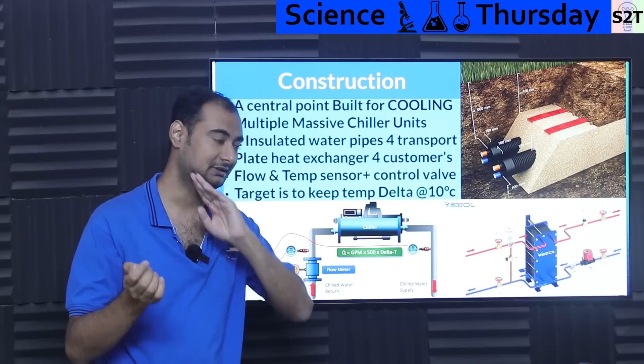So the computer will detect it. The computer is like, okay, let's choke the flow. It will start to slow down the flow, and until it reaches 10 degrees Celsius, it will try to keep it as stable as possible. Now, let's say it opened the max flow, and then you are dumping so much heat into it that the return water, instead of being 15 degrees Celsius, is at 18 degrees or 20 degrees Celsius. They're gonna call you up. It's like, bro, something is wrong. Either your heat exchanger is not up to the scale, or you're overloading it too much.